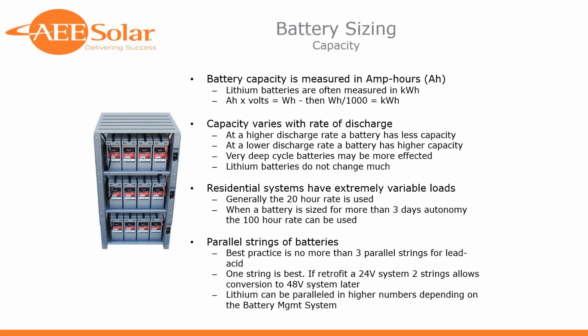Now, usable kilowatt hours, of course, you then have to take into account the battery depth of discharge that you want, and also the inverter efficiency, which is often forgotten. Inverters are not 100% efficient. In general use, I use 87% efficiency for the better inverters that we sell. And of course, you have to size the battery that much larger to compensate for the inefficiency of the inverters to power the loads that you want to power.